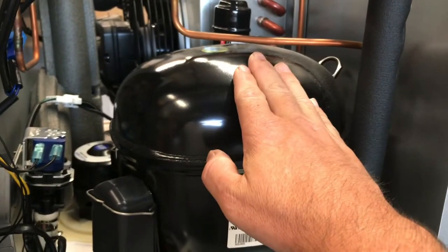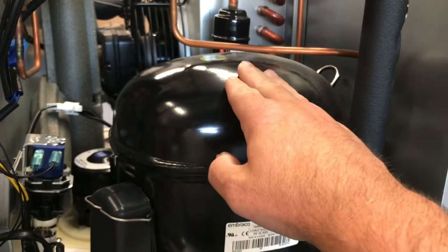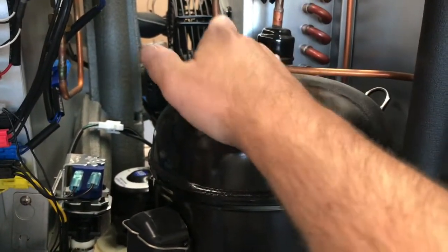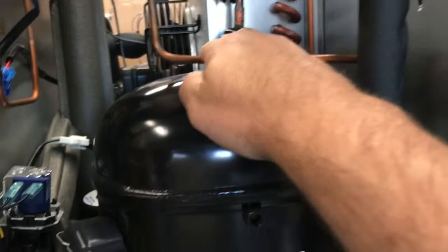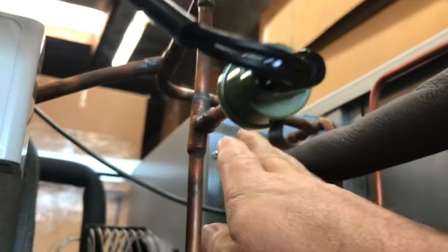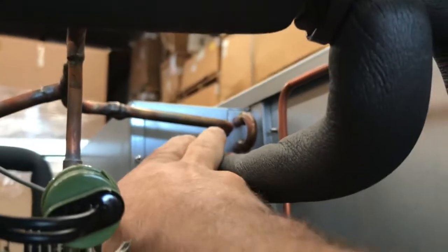The compressor compresses your vapor refrigerant into a high temperature, high pressure vapor. It comes out of this discharge line, which is going to be the same as this right here. This is your discharge line coming off the compressor. So it comes out of this discharge line, it travels up, it's a little hard to see it. It's going to travel up, come over, go to the right here and go into this condenser. This is the condenser on an ice machine.